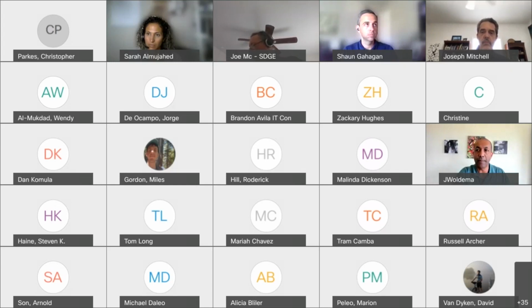Yeah, it's a combination of things. A lot of our distribution transformers would have to be replaced because we have a lot of single-phase conductors and single-phase transformers. Additional phases would need to be installed to balance the capacitance needed to accommodate the REFCL technology, which works by taking the unfaulted phases and transferring the energy over to reduce the fault and send it to ground. So it would take changing out a lot of transformers and upgrading conductor to covered conductor to reduce the risk associated with wire downs.